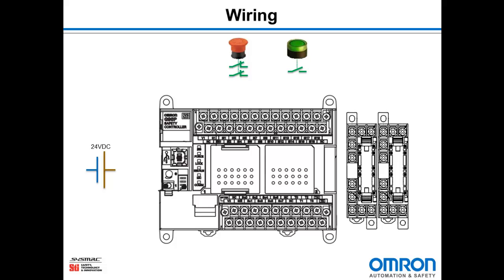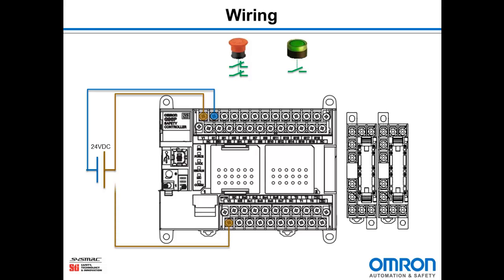So the first thing we need to do is wire up the power. I need to connect 24 volts into the V1 and 0 volts to the G1 terminal on the top of the G9SP, and I also need to wire into the V2 and G2 terminals at the bottom of the G9SP. That's for the output power.